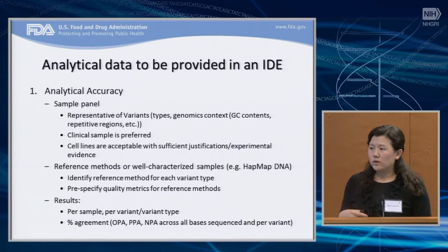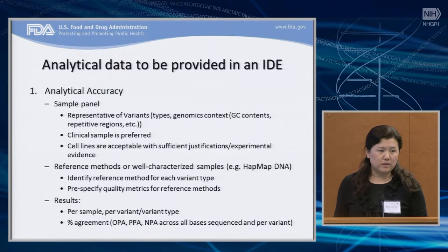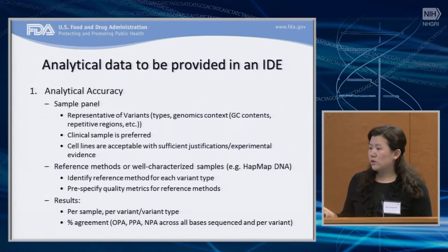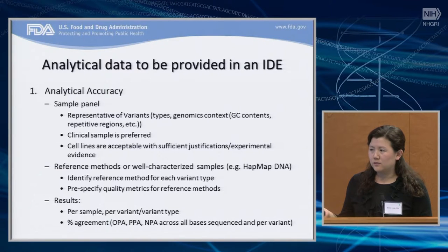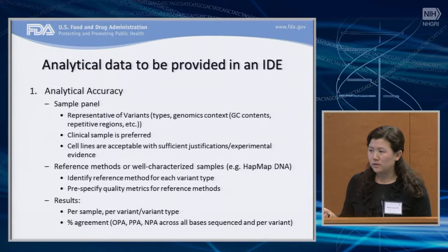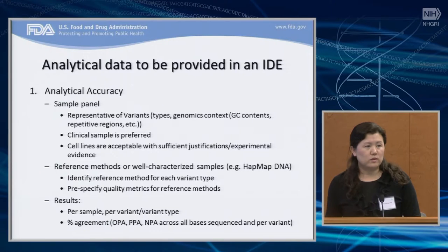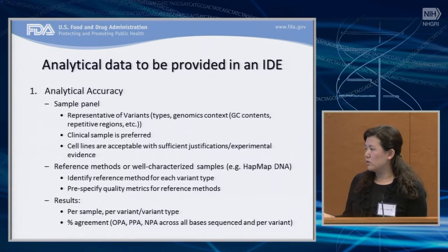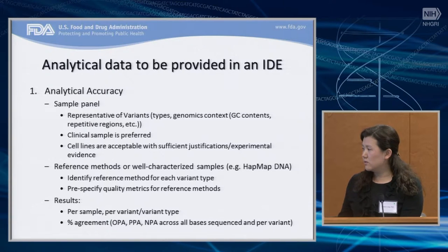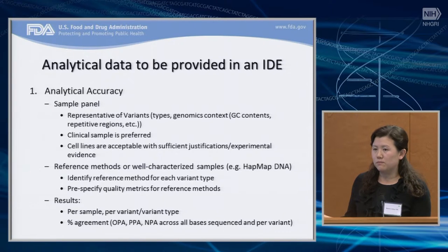For the reference method, we accept analytically validated comparator methods. If you have a reference method, you will summarize results as sensitivity and specificity. If you don't have a reference method and use a comparator method, then you will show the result as percent agreement — showing similar metrics, just with different terminology. It's important that reference methods be pre-specified with acceptance criteria and how they will be used. Results need to be summarized by sample and by variant types in terms of percent agreement: overall percent agreement, negative agreement, and positive agreement.